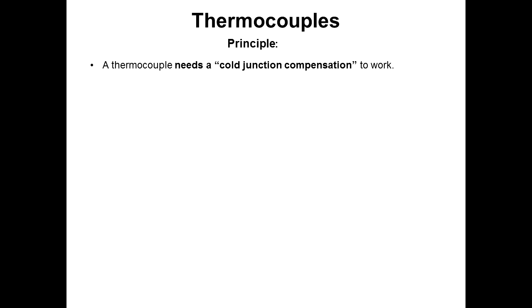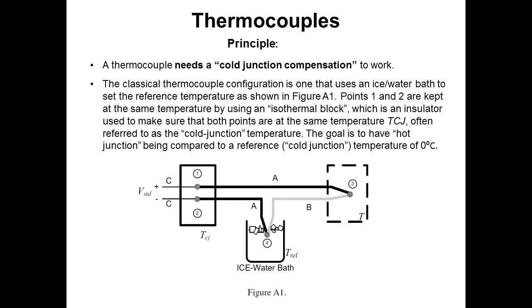A thermocouple needs a cold junction compensation to work. The classical thermocouple configuration, the original ones, used an ice bath, water bath, to set as a reference temperature, as shown in this figure 1. Points 1 and 2 are kept at the same temperature by using an isothermal block, which is an insulator used to make sure that both points are at the same temperature. The cold junction temperature is here using this ice bath, and it's referenced to a temperature of 0 degrees C.